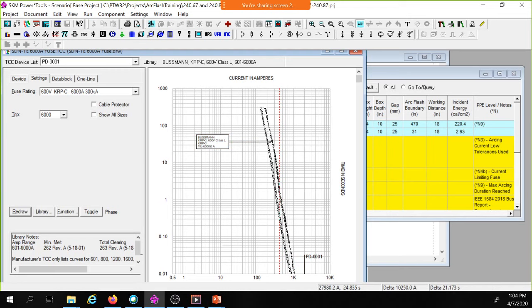Now, if I lower the size of that fuse and move my trip curve, look at where my arcing current is now tripping faster, a little over 0.01 seconds. That's why my incident energy goes down.